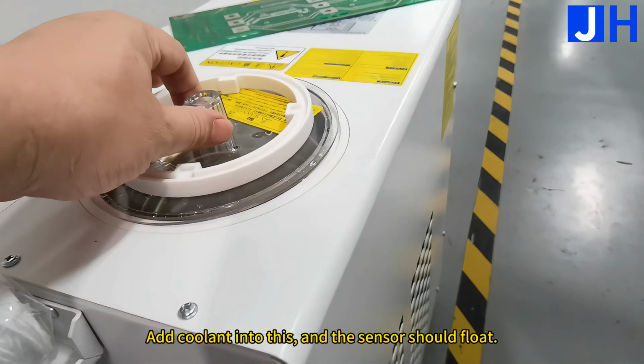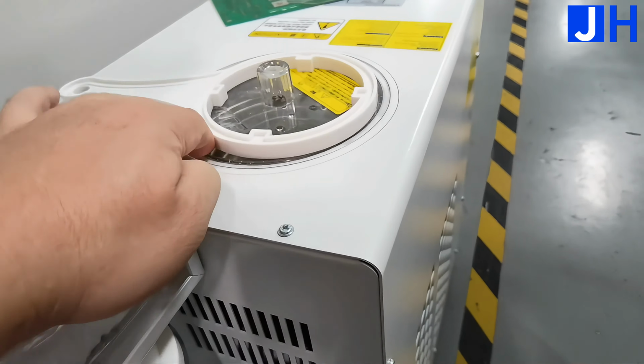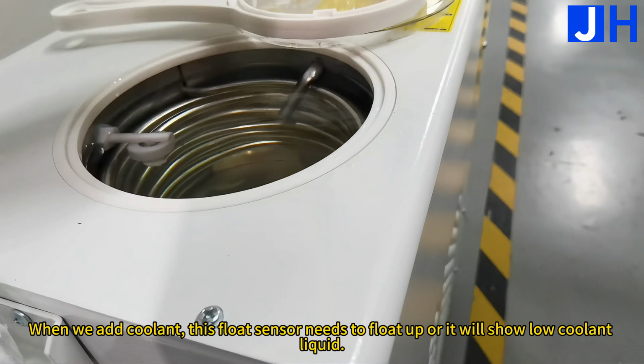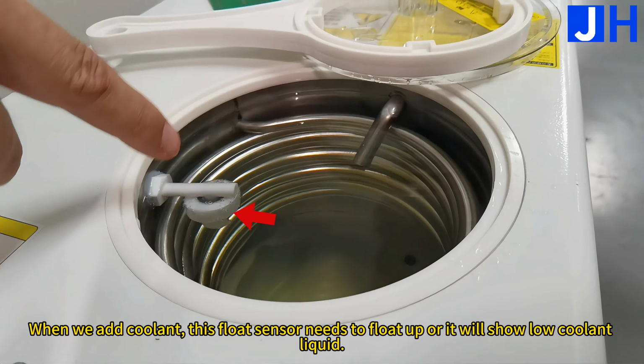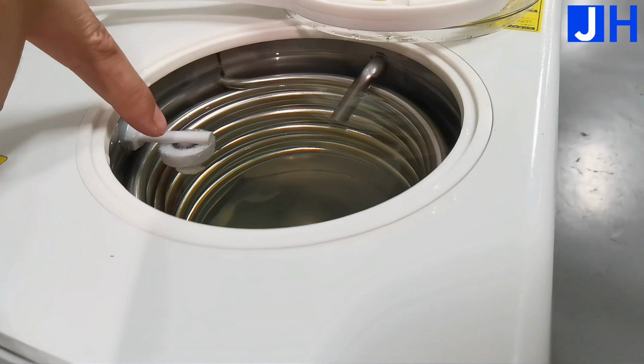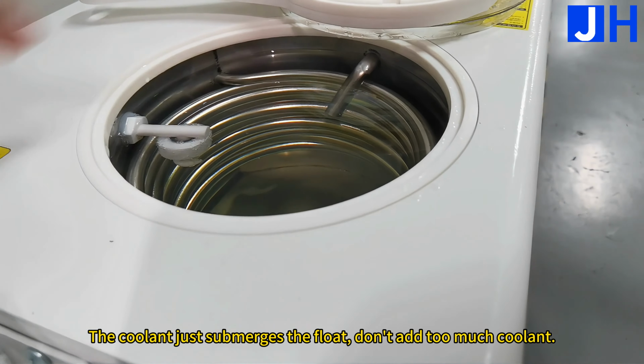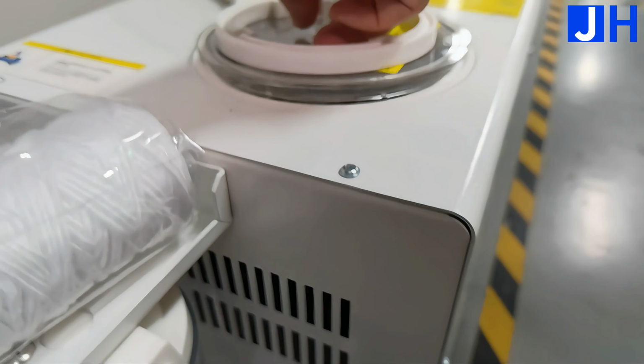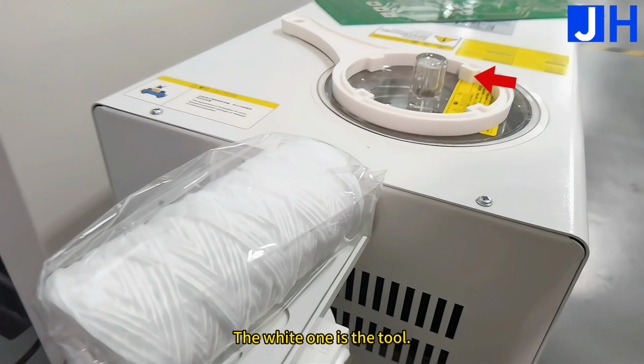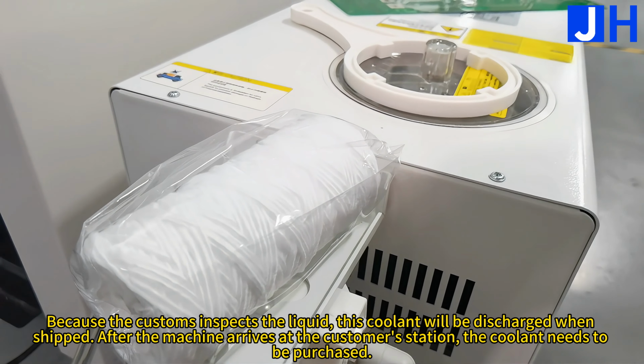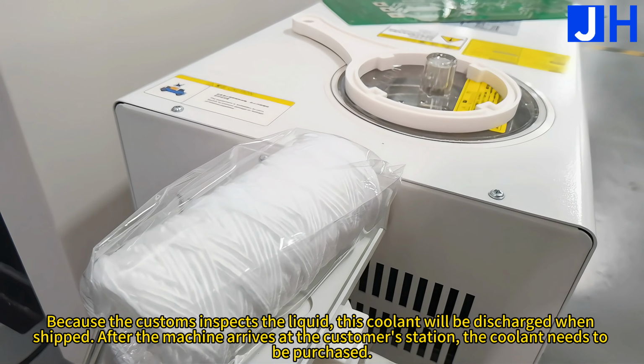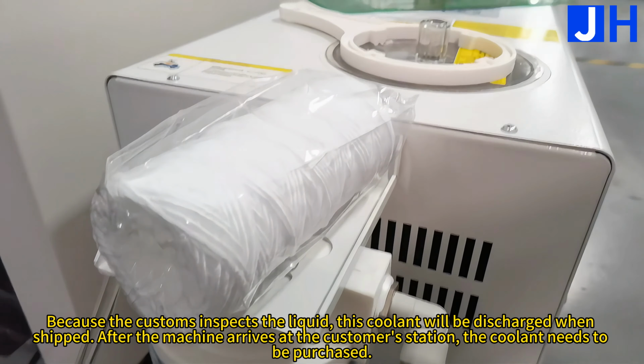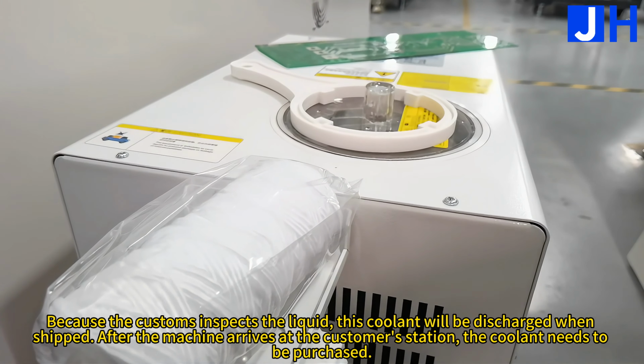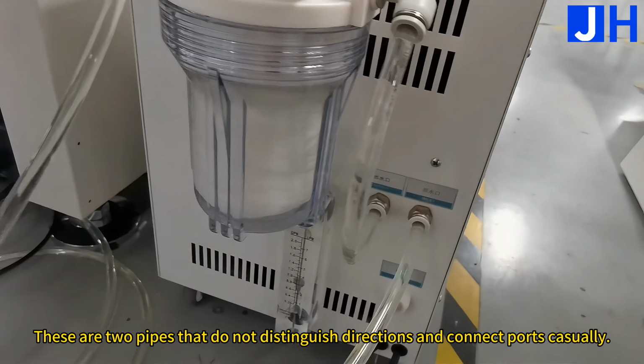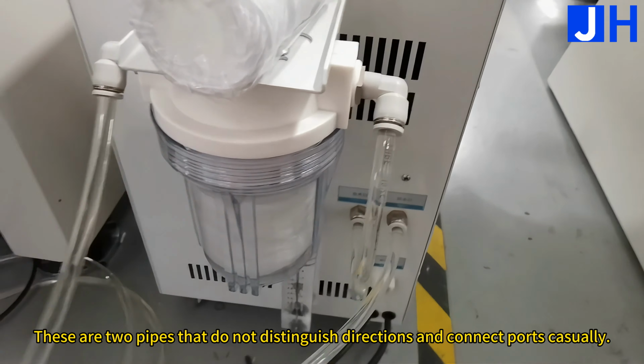Add coolant into this, and the sensor should float. When we add coolant, this float sensor needs to float up or it will show low coolant level. The coolant should just submerge the float, so don't add too much. The white one is the tool. Because customs inspects liquids, the coolant is discharged when shipped. After the machine arrives at the customer's station, the coolant needs to be purchased. These are two pipes that do not distinguish directions, so connect the ports casually.